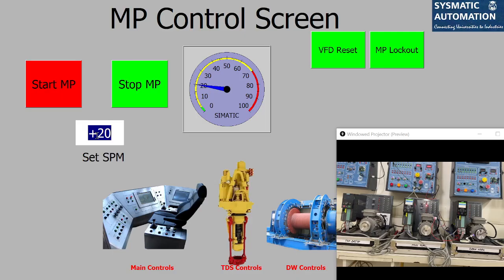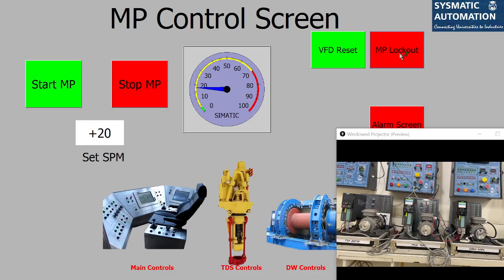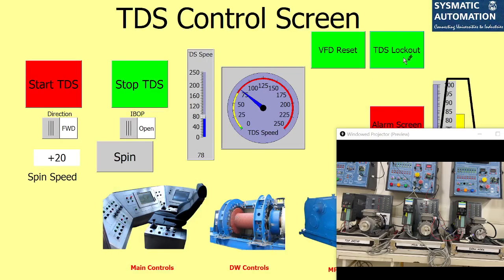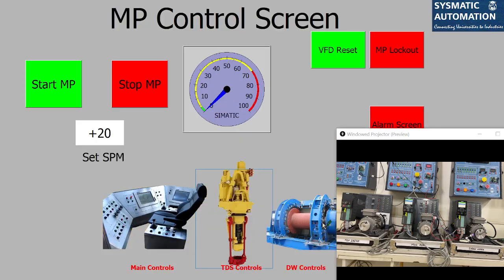So my mud pump is running, and now if I press the lockout on any of these units, the units will stop immediately, because this is a safety interlock that we have. Same way with the top drive: if I press the lockout, the top drive stops, right? If I remove the top drive lockout, it still shows an alarm here because my mud pump is in lockout condition. So I'll go back and remove the lockout on the mud pump. So this is my mud pump operation and top drive operation.